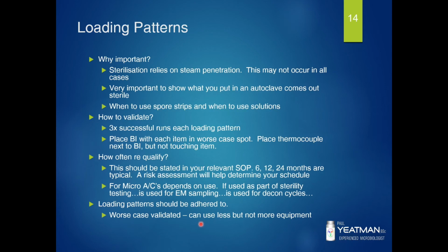You validate the worst case, so you could put less in the autoclave than the worst case. So if you've got, say, 20 by 1 litre containers in there, you could put in 10 by 1 litre containers. But you wouldn't go 21 1 litre containers or more because that's greater thermal load than what you validated. So you can always go less.